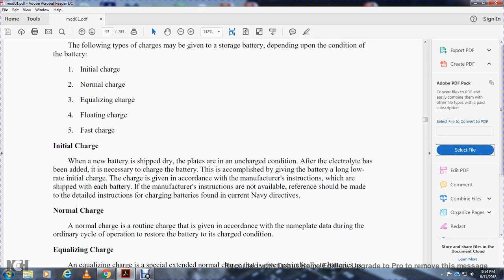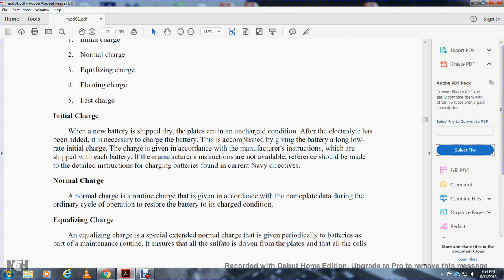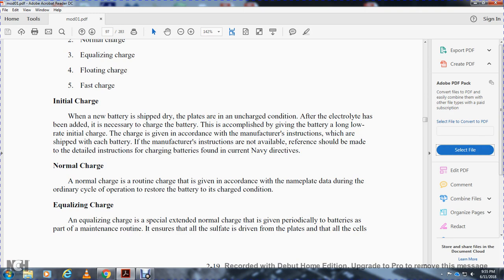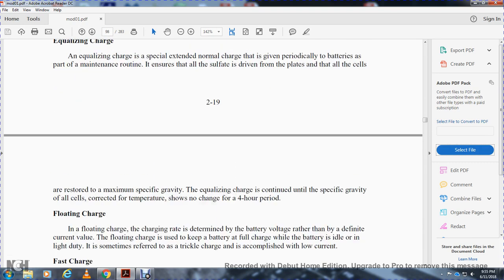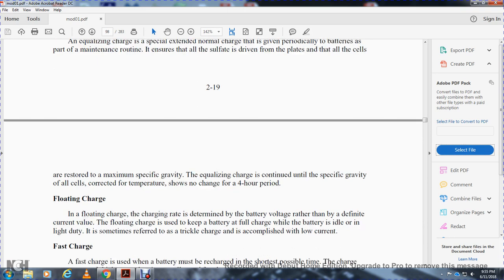Batteries are usually charged in a battery shop, which has specific charge procedures for each type of battery. Types of charges include: initial charge, normal charge, equalizing charge, floating charge, and fast charge. Initial charge: when new batteries are shipped, the plates are in an uncharged condition; after electrolyte is added they must be given an initial charge at a low rate according to the manufacturer's instructions. Normal charge is a routine charge given according to the nameplate data during the ordinary operating cycle. Equalizing charge is an extended normal charge given periodically to ensure all sulfate is driven from the plates and all cells are restored to maximum specific gravity.